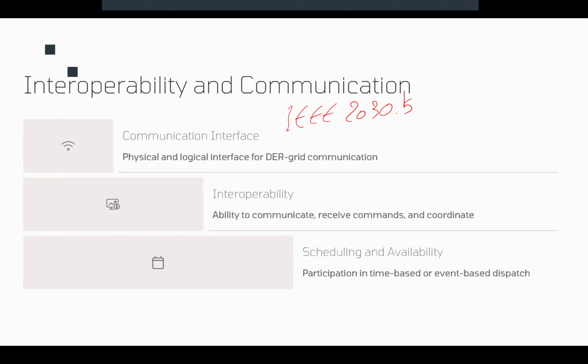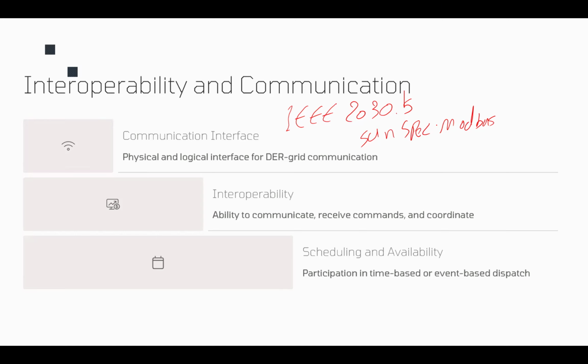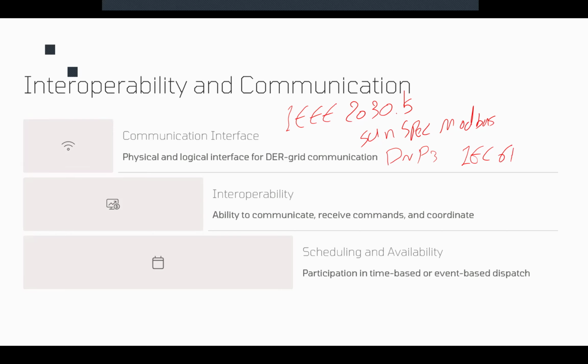Another standard that is required by IEEE 1547 is called SunSpec Modbus, okay, which is a lightweight and widely used protocol for local monitoring and configuration. Okay, normally inverter manufacturers use that. It's very common in inverter manufacturers. Another required standard and protocol is DNP3 or IEC 61850, which is normally preferred for utility SCADA integration.